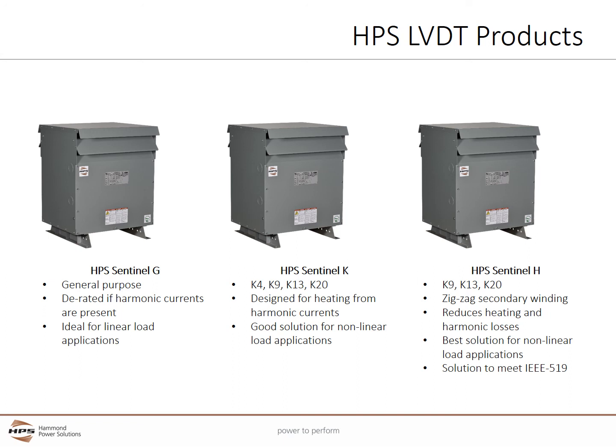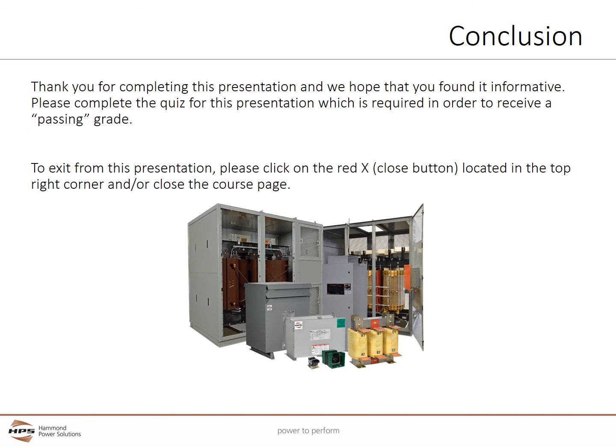The HPS Sentinel-H is a harmonic mitigating design that is also K-rated. The zigzag secondary windings cancel some harmonics and improve power quality. The Sentinel-H reduces overall heating and harmonic losses compared to the K-rated and general purpose transformers. It is the best solution for non-linear load applications and can be an integral solution to meeting IEEE 519. Thank you for completing this presentation. We hope you have found it informative.